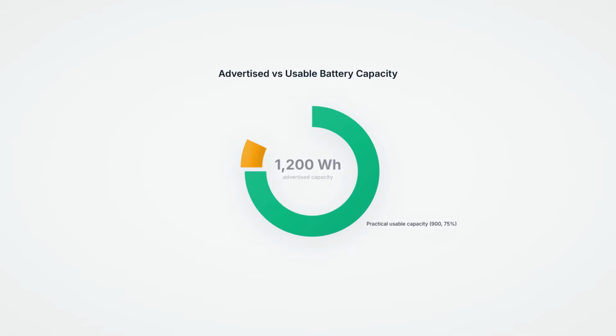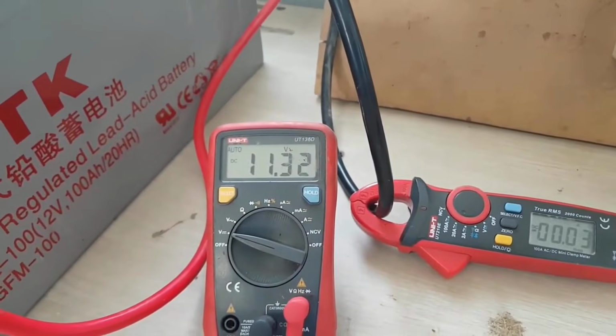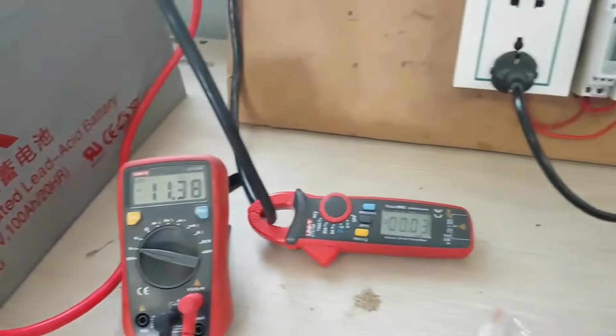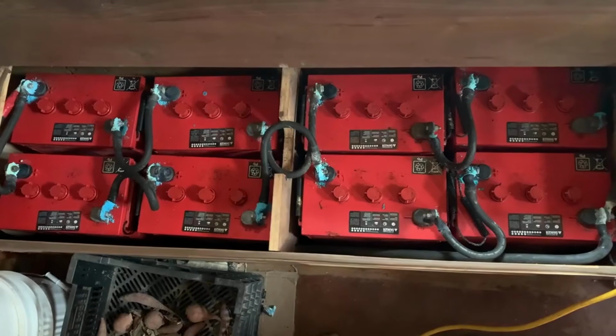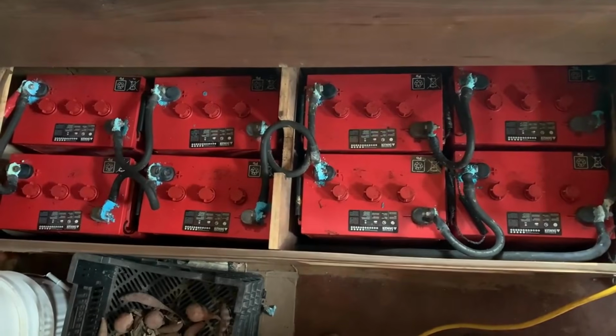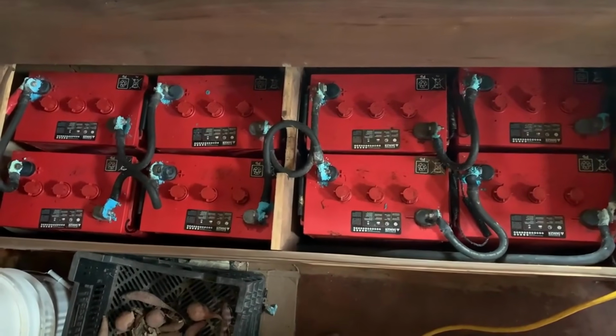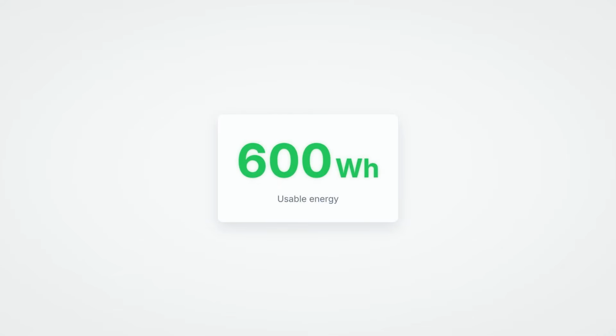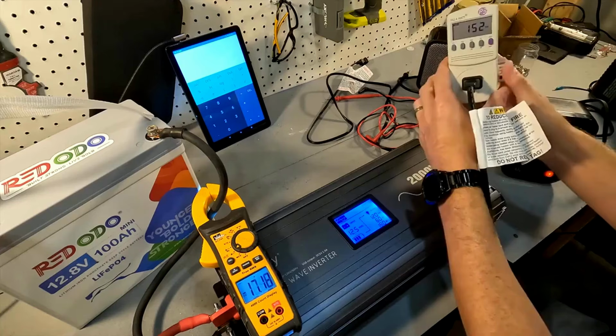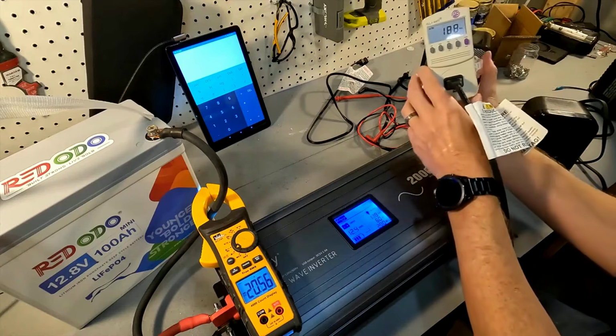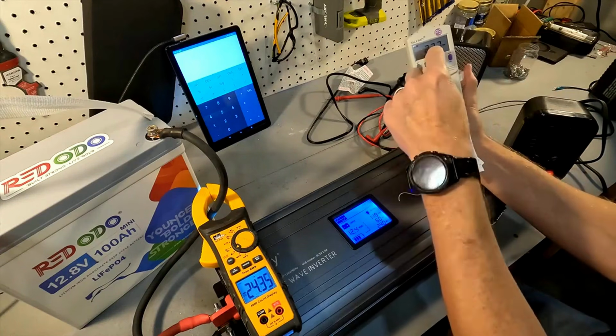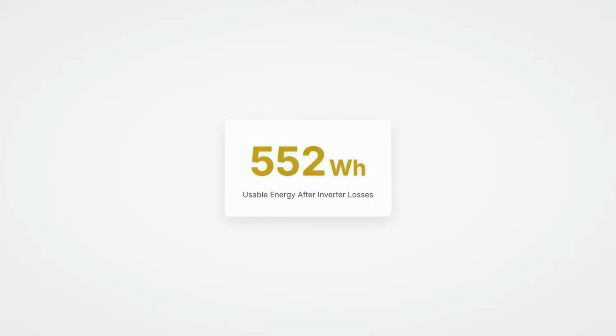Here is where the label math breaks. A 12-volt, 100 amp-hour lead-acid battery advertises 1,200 watt-hours, but discharge a lead-acid below 50% regularly, and you accelerate capacity degradation fast. Usable energy is closer to 600 watt-hours. Then subtract inverter conversion losses, typically 10 to 15%. You are now at roughly 510 watt-hours before the battery dies early.